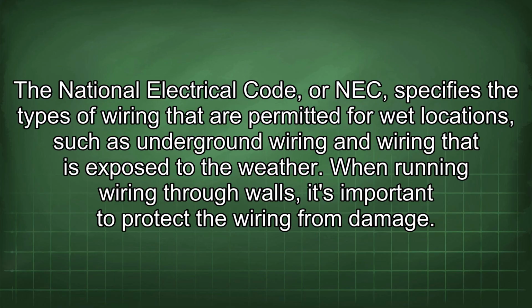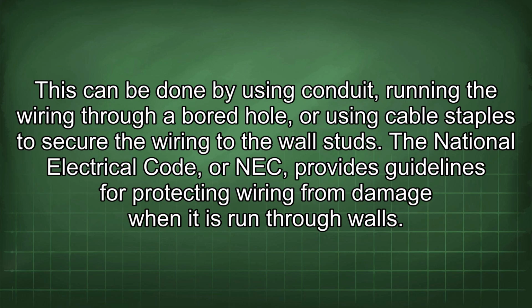When running wiring through walls, it's important to protect the wiring from damage. This can be done by using conduit, running the wiring through a bored hole, or using cable staples to secure the wiring to the wall studs. The National Electrical Code, or NEC, provides guidelines for protecting wiring from damage when it is run through walls.